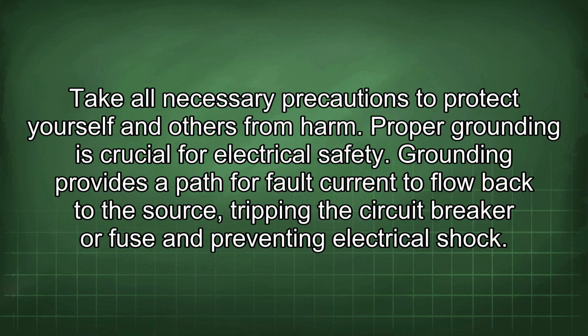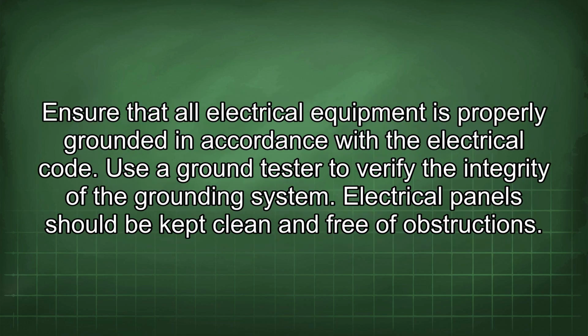Proper grounding is crucial for electrical safety. Grounding provides a path for fault current to flow back to the source, tripping the circuit breaker or fuse and preventing electrical shock. Ensure that all electrical equipment is properly grounded in accordance with the electrical code. Use a ground tester to verify the integrity of the grounding system.